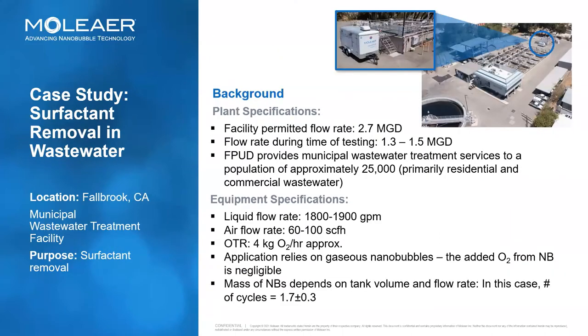In this case study, Moleaer set out to further validate the benefits of nanobubbles as a pretreatment to the activated sludge process. Fallbrook, California Municipal Wastewater Treatment Facility offered to host this testing. Initially, we ran a small flow pilot test to confirm that we could expect positive results at this facility. Based on those positive results, we then set up our equipment for a full scale test, which would treat all of the influent coming into this treatment facility. The facility is rated for 2.7 MGD but currently operates between 1.3 and 1.5 MGD, serving 25,000 primarily residential and some commercial customers. Our equipment consisted of an 1,800 to 1,900 GPM pump with an airflow rate of 60 to 100 SCFH, equating to an oxygen transfer rate of approximately four kilograms of oxygen per hour — negligible relative to the size of the plant.